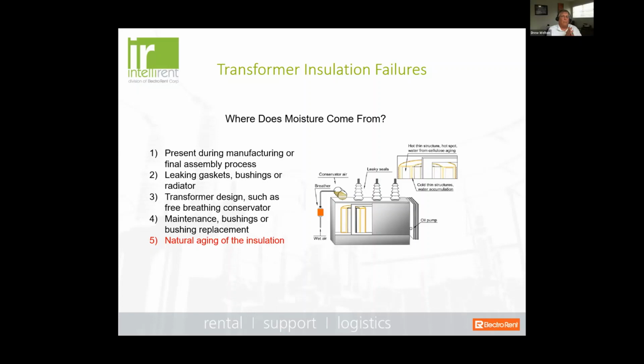Okay, so if we're concerned about moisture, we have to understand where moisture comes from. A number of years ago, I was out in Colorado at a local utility, and we were talking about moisture in transformers. And one of the comments from the engineers was, well, we're at a high elevation here. We have very little relative humidity in the air. And I said, well, that's understandable, okay, because whenever you have a leaky bushing, or you're doing maintenance on a bushing, or you're exposing the tank to any kind of outside atmosphere, you always have the opportunity to have moisture ingress. But moisture can be present during the manufacturing or final assembly process.